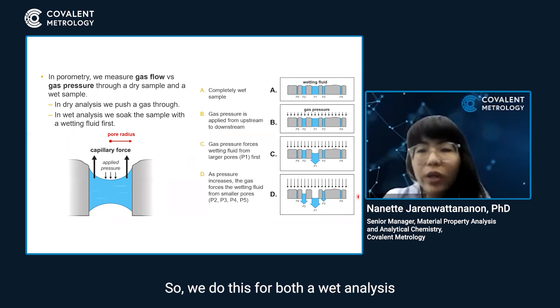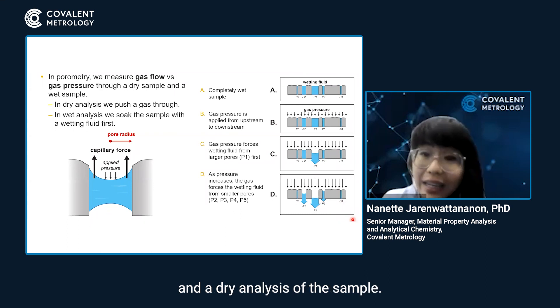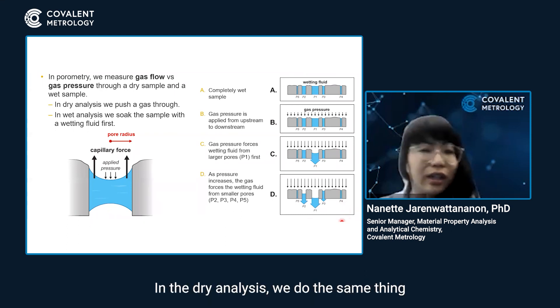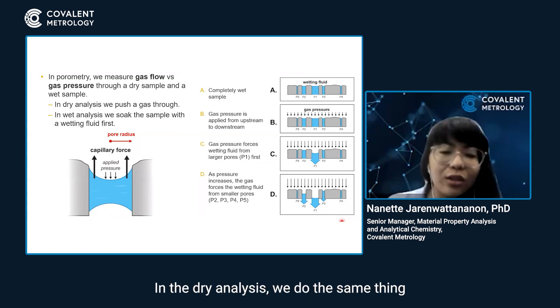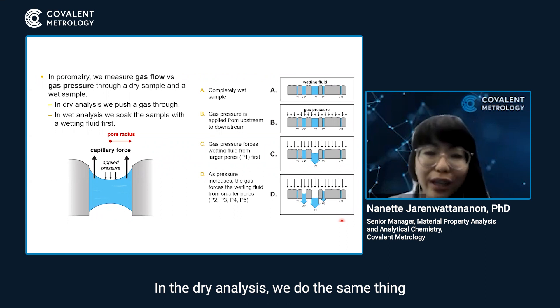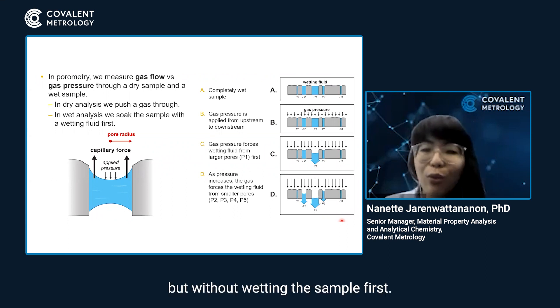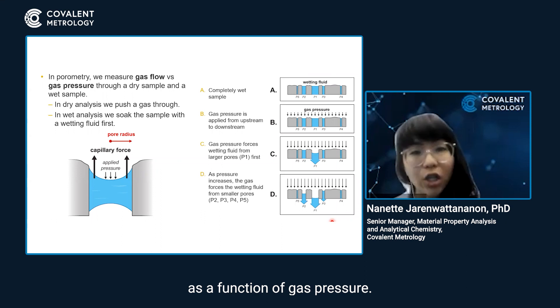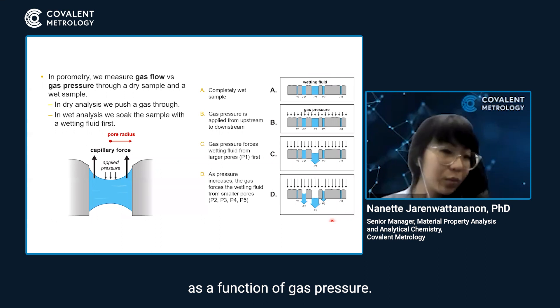We do this for both a wet analysis and a dry analysis of the sample. In the dry analysis, we do the same thing but without wetting the sample first — we basically just measure gas flow as a function of gas pressure.